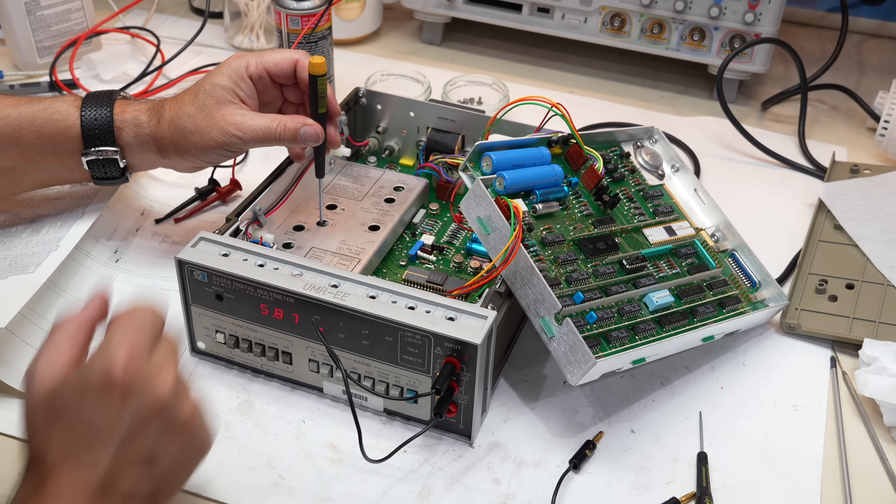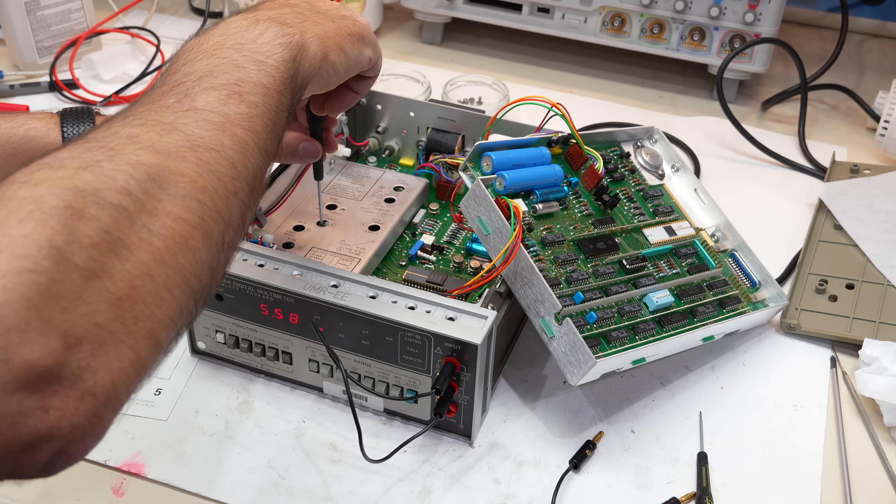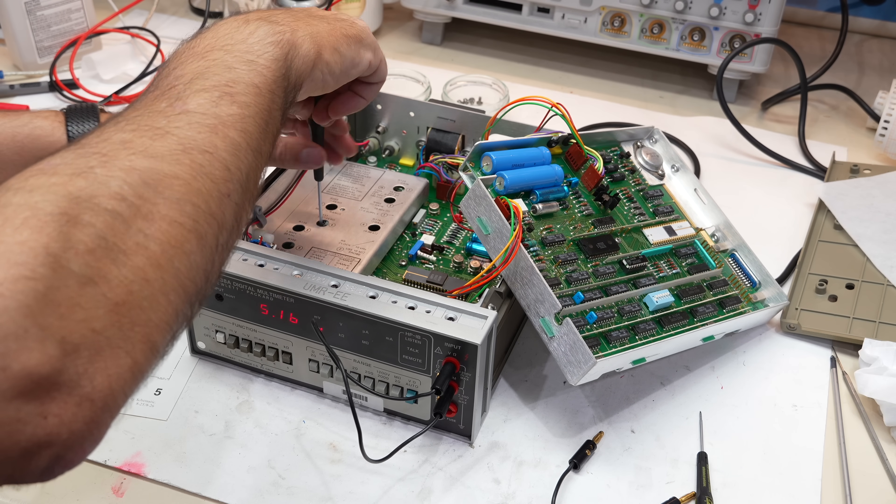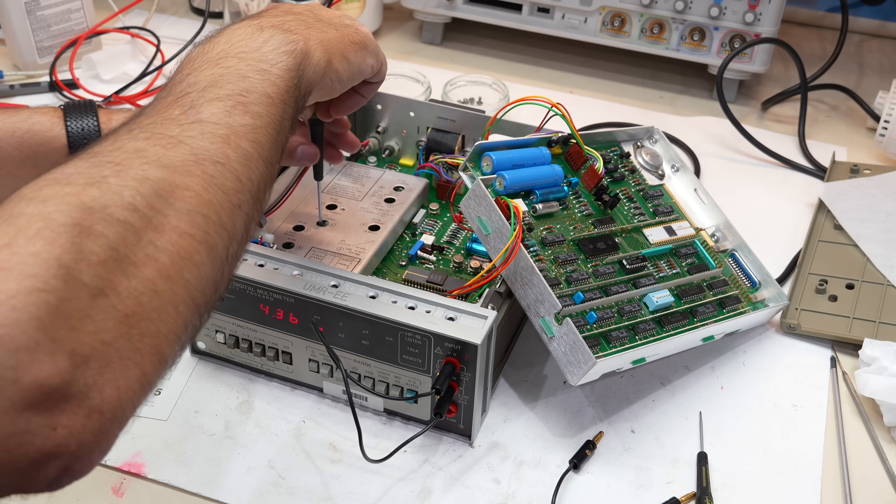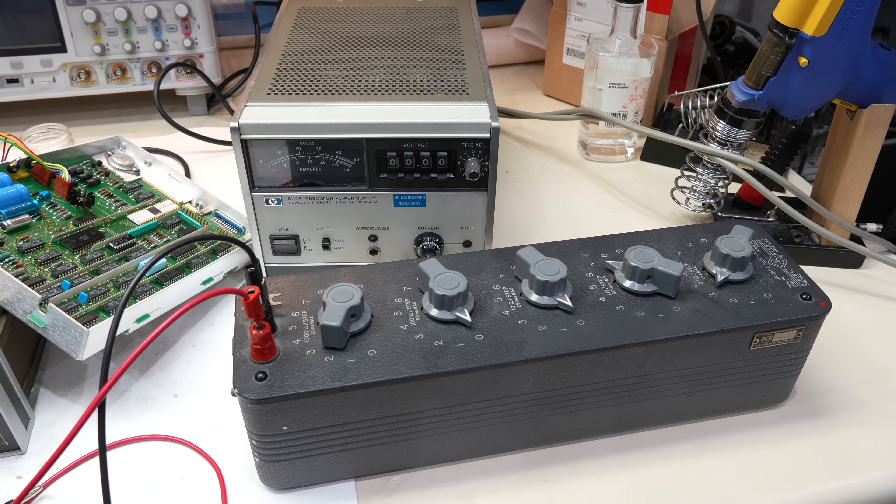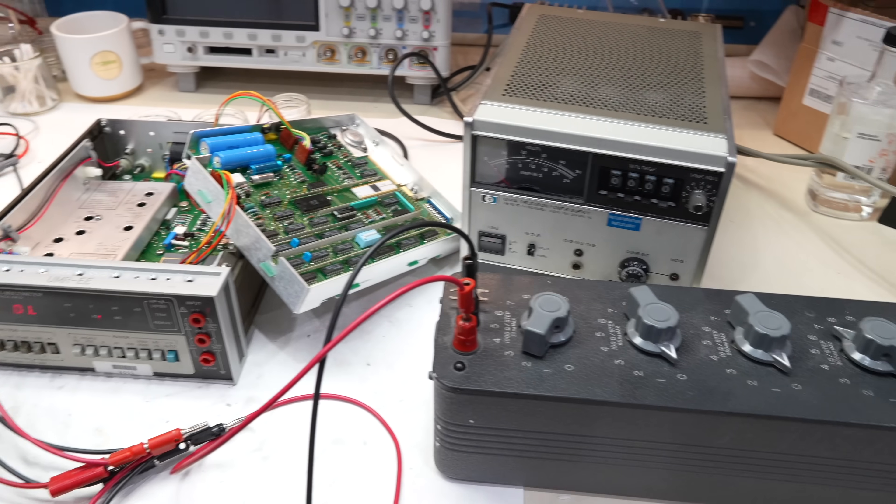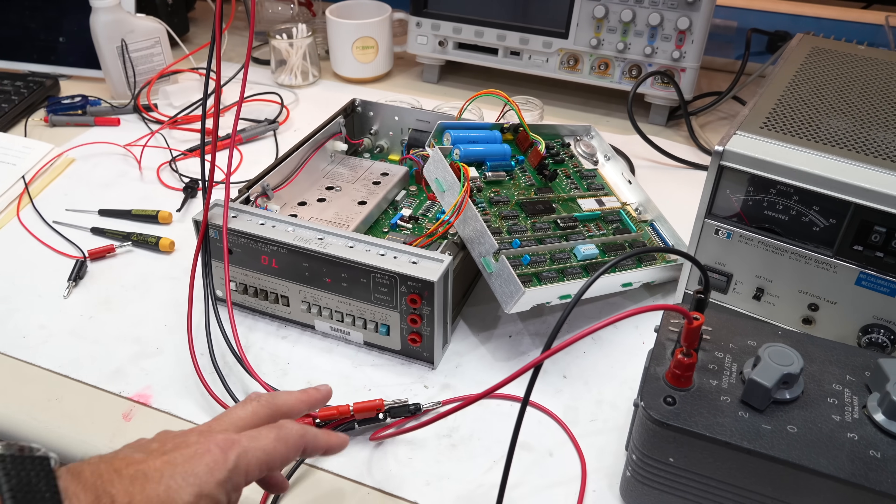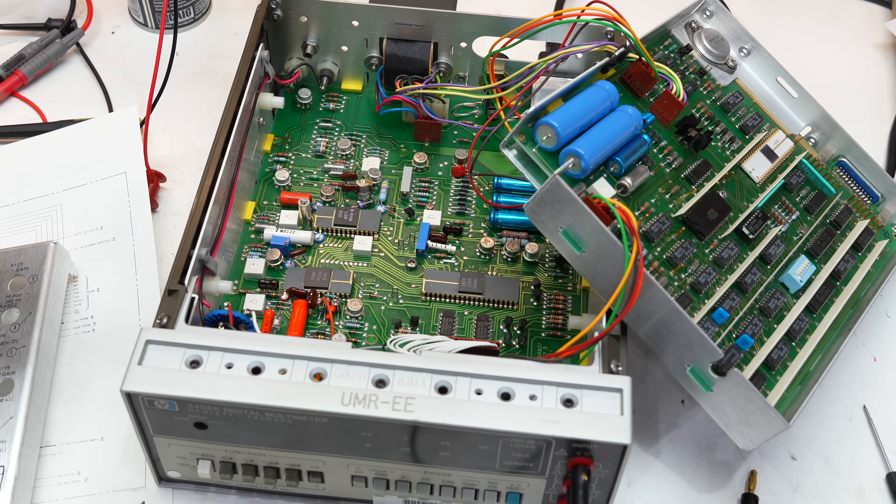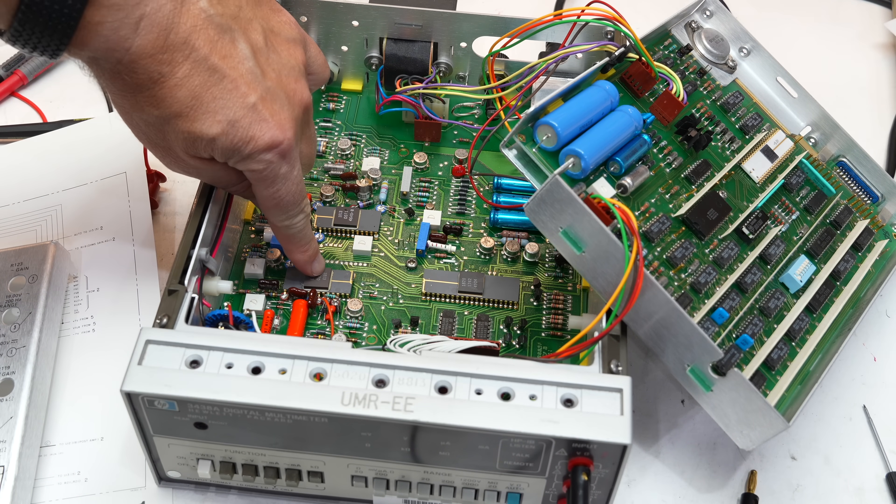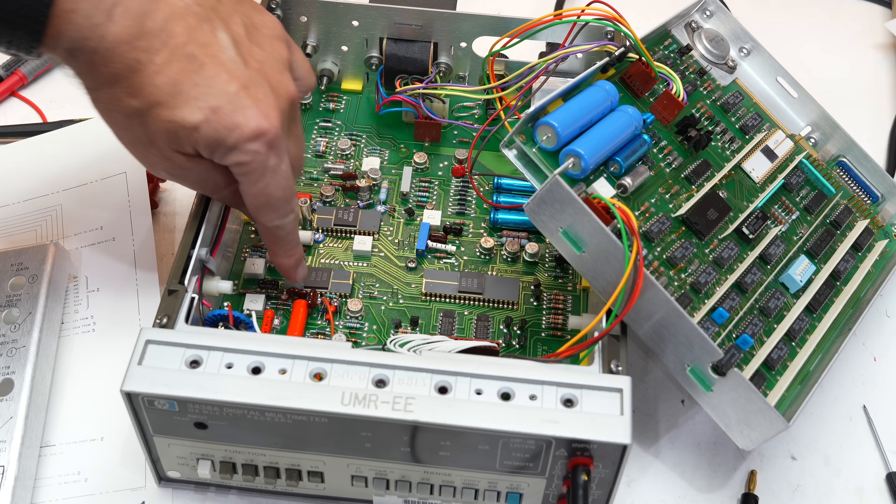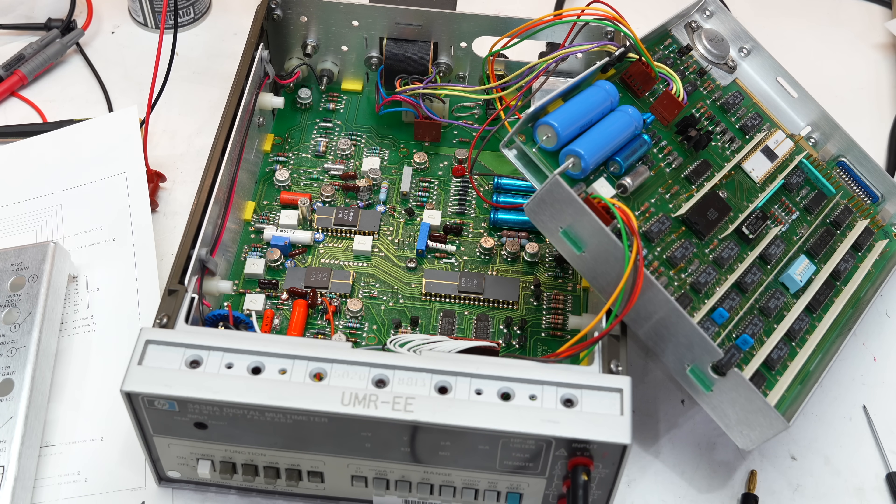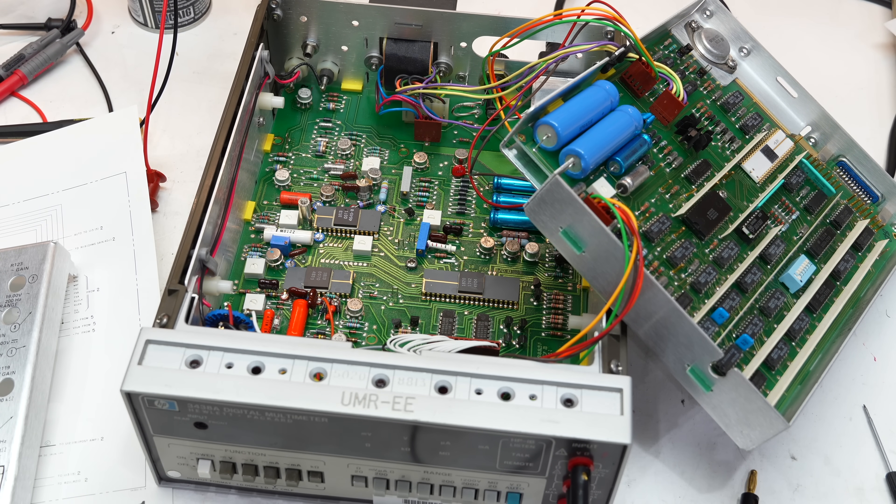The ohms did work somewhat, but I could not zero out the 20 and 200 ohms ranges properly. Moreover, I could only calibrate the 2k ohms range successfully. At the time, I blamed it on the HP proprietary hybrid which contains the analog switches and the precision resistors that control the current source, which is then used for all the resistance measurements.